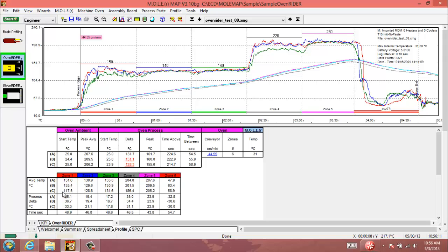It's the averages of all the data logs that are taken at one tenth of a second in the oven rider palette. It will show you that for each zone as well as the process delta. These are your process sensors - essentially how much they change in temperature as they progress through each zone. You can see here process sensor A changed 36 degrees from the beginning of zone one to the end of zone one, and so on for the other process sensors and other zones.